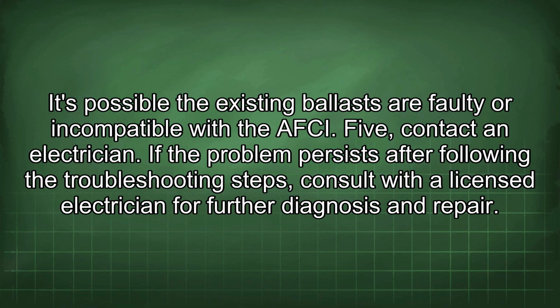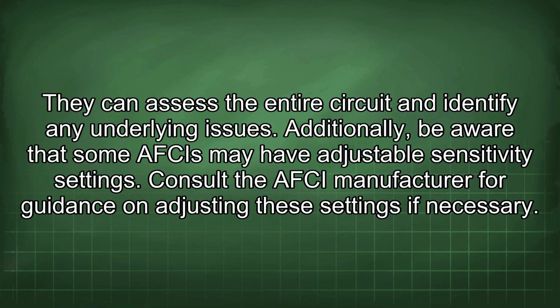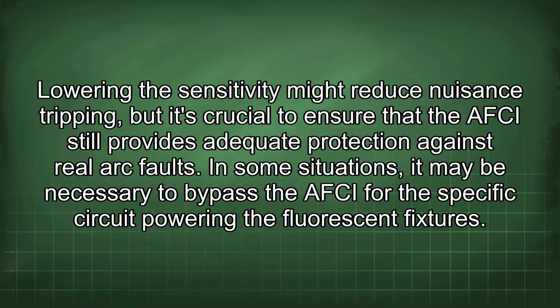5. Contact an electrician. If the problem persists after following the troubleshooting steps, consult with a licensed electrician for further diagnosis and repair. They can assess the entire circuit and identify any underlying issues. Additionally, be aware that some AFCIs may have adjustable sensitivity settings. Consult the AFCI manufacturer for guidance on adjusting these settings if necessary. Lowering the sensitivity might reduce nuisance tripping, but it's crucial to ensure that the AFCI still provides adequate protection against real arc faults.